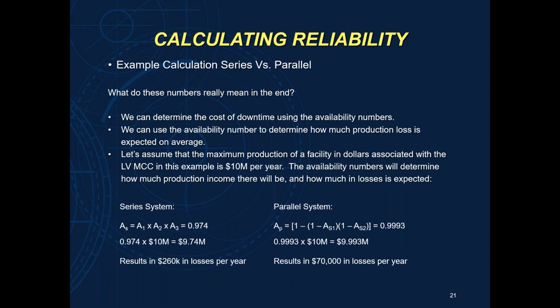So let's apply that to our calculations that we have on the bottom. We can see that in our series system, based on the availability number, we are producing $9.74 million per year. So we're experiencing $260,000 in losses per year. On the parallel system, we are now experiencing $70,000 in loss per year compared to the series system of $260,000. So we are now netting $190,000 extra per year because we decided to install a parallel redundant system as opposed to a series system.